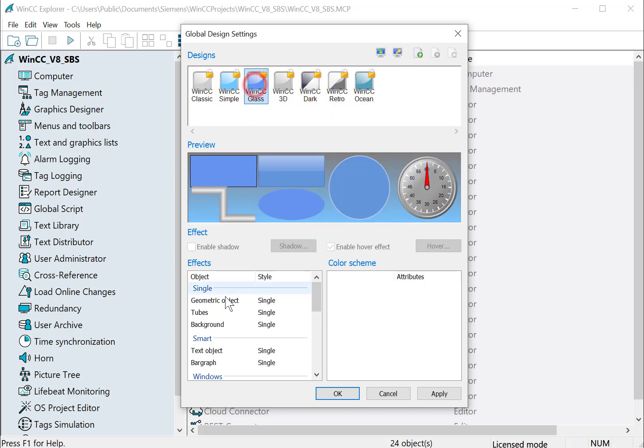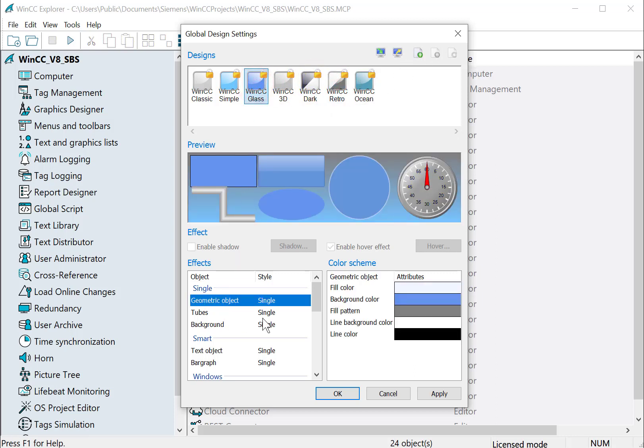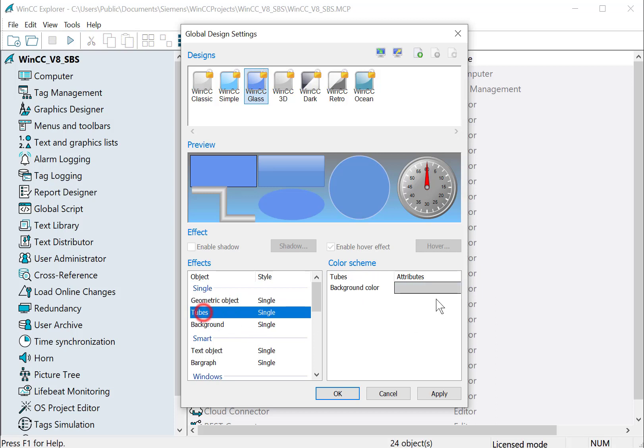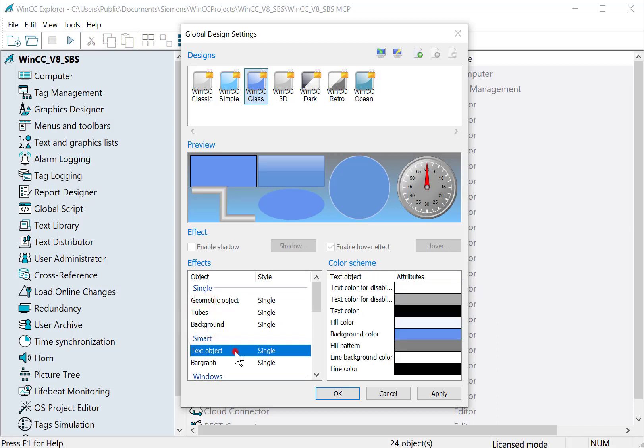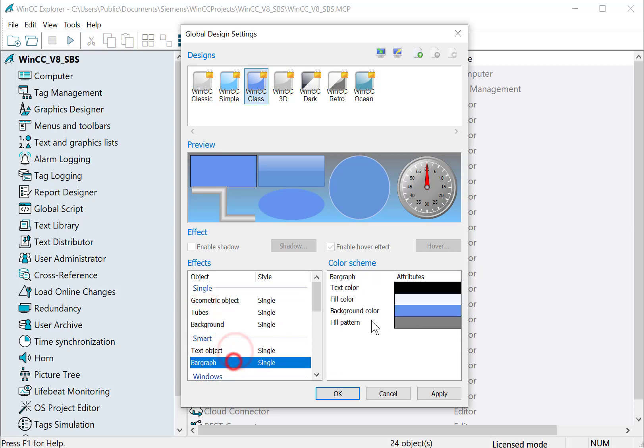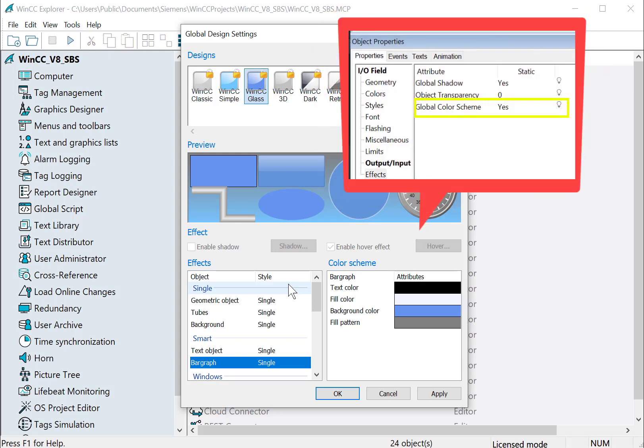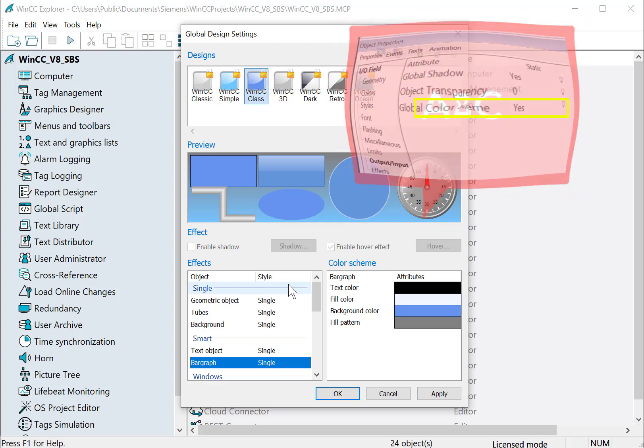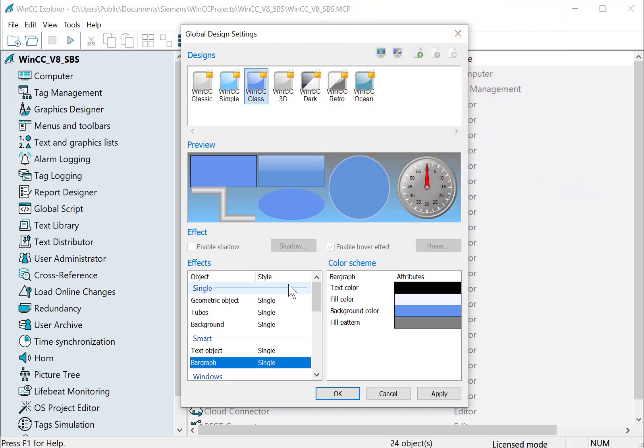But basically, this allows you to select different objects and define exactly how they look so that when you add them to screens, they're already configured and you have a user interface that conforms to this design. And we're going to see when we get into Graphics Designer that there's a property on pretty much every object that is whether or not it subscribes to the current global design or not. And before you can make changes, you have to set that to no. So we'll see that when we get into Graphics Designer.